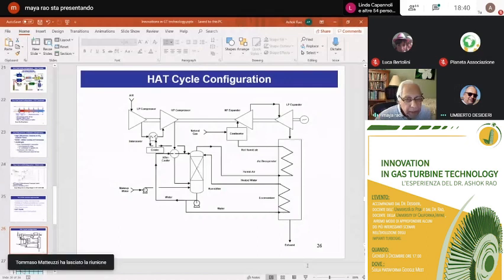A challenge here is, of course, to preheat the oxygen going back to the combustor. They do it by premixing some of the recycled gas to limit the oxygen partial pressure. That's important from a metallurgy standpoint in the recuperator, because at high partial pressure of oxygen, the steel can catch fire.